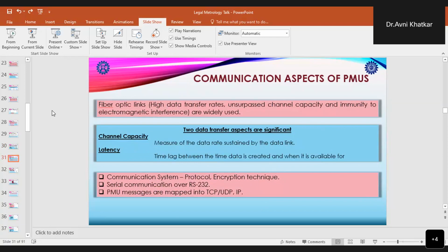Now, when we talk about the communication aspects of PMUs, the communication system for all the PMUs should be based on fiber optics. Even in the URTDSM scheme, this was the recommendation that the communication system for the PMUs will be fiber optics, because if we are using fiber optics, we have higher data transfer rates, unsurpassed channel capacity, and these are also immune to any type of electromagnetic interference. Hence, fiber optic links are widely used.